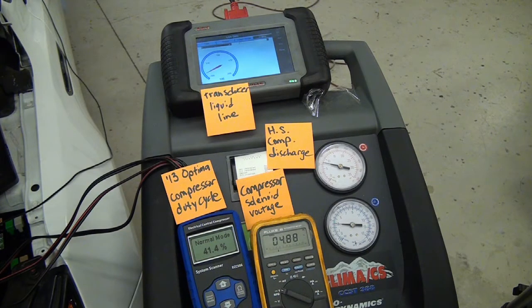The transducer is being read by the scan tool up top. That's in the high pressure liquid line, and it's reading about 106 psi. So what we're going to do now is increase the heat load on this system and watch what changes take place on these meters.